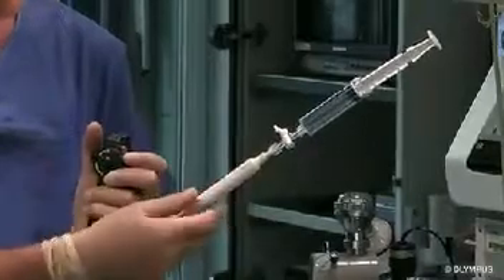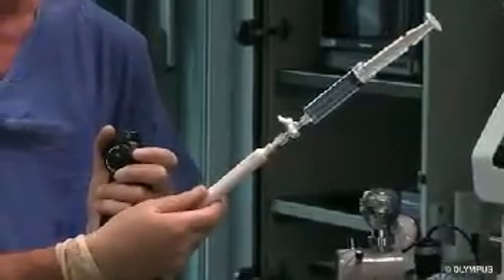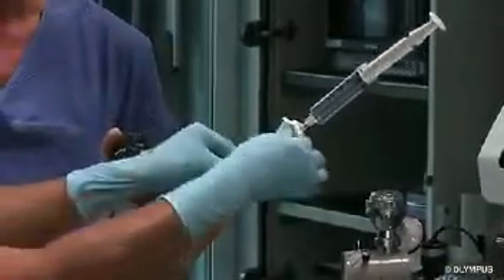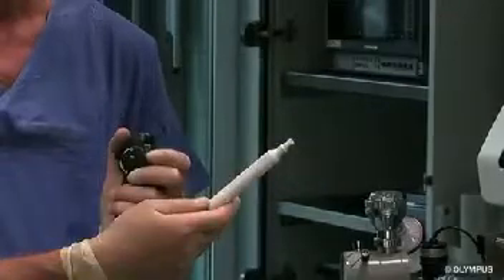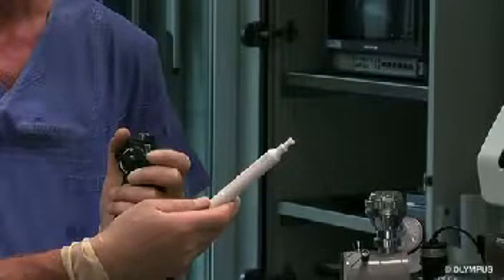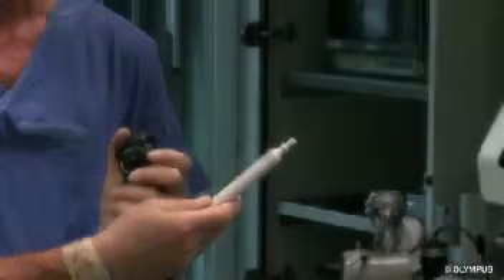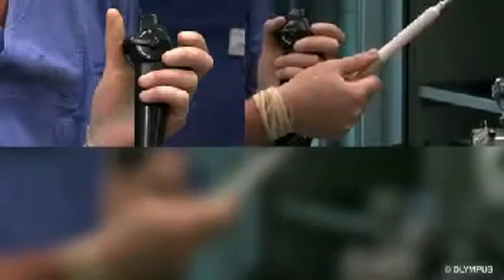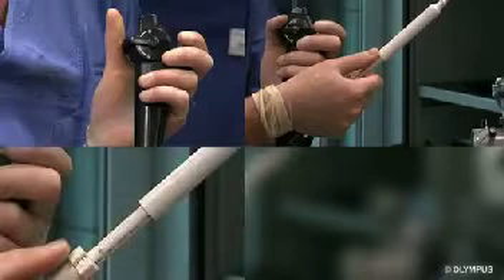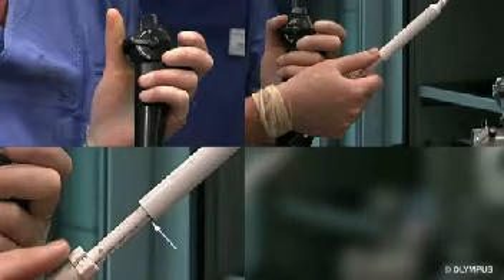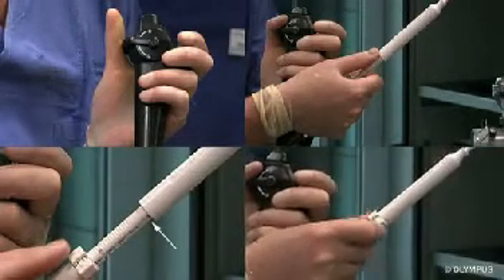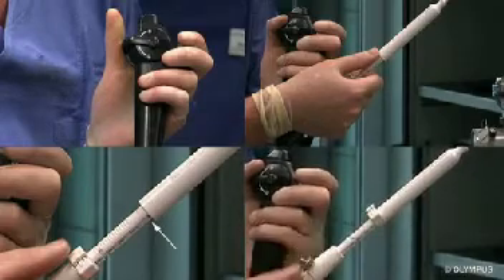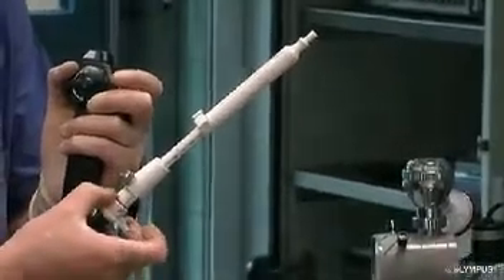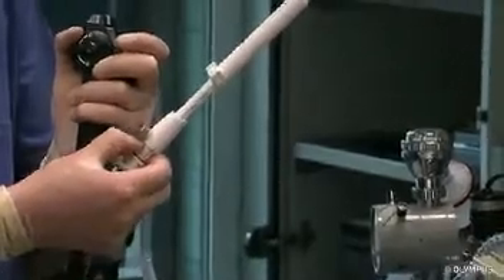Before retracting the needle from the lesion, the vacuum has to be equilibrated by removing stopcock and syringe from the needle. Before withdrawing the needle from the endoscope, these steps must be followed to avoid damage to the endoscope. Straighten the endoscope. Fully retract the needle slider until a click is heard. Confirm you can see the control line on the needle scale. The adjuster lever has to be used to fix the needle slider. Then the needle is disconnected and removed from the endoscope.